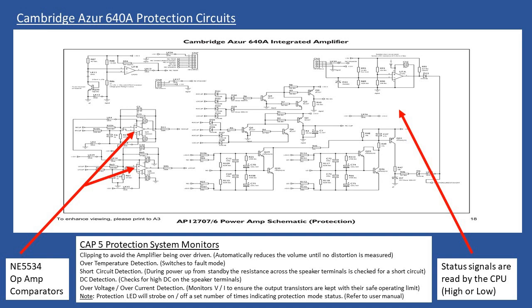But what is more difficult when you come to fault finding is maybe the protection circuit operates and you only have one common startup relay, and the design is such that that is what will operate. And then it de-energizes the power relay, switches off the main toroidal transformer or power transformer, and that's it. So you can imagine when you're fault finding, and I appreciate for many of you who are listening to this audio tutorial, you're often in that world, you're unable to make any voltage measurements because there's no longer any power applied.